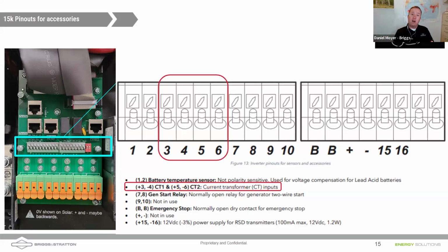So maybe we are able to do time of use where we can discharge to the main non-backed up loads when grid is up, so that we're not drawing from grid. So that's one scenario, right? And we can use some of your PCS controls to do that. So we're sending power back to the main non-backed up load center, but not so much that it goes back onto grid. We also see that we have more accuracy. So after I just kind of summarize that, do you recommend installing CTs even though you have them built in? What are your thoughts? I'd say it depends on the installation.